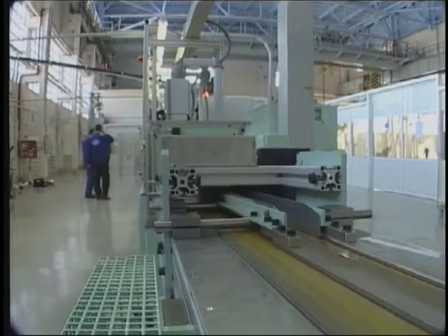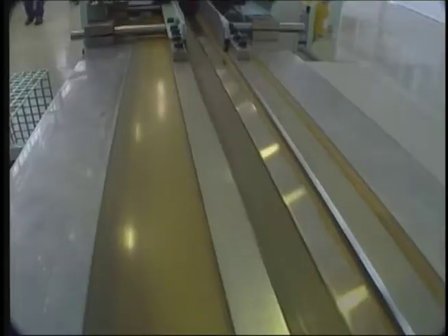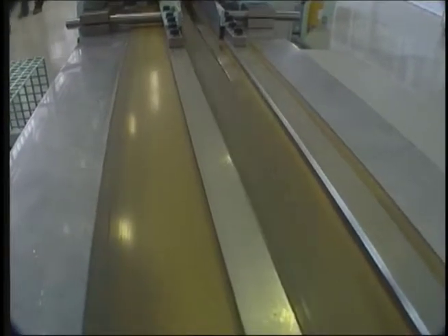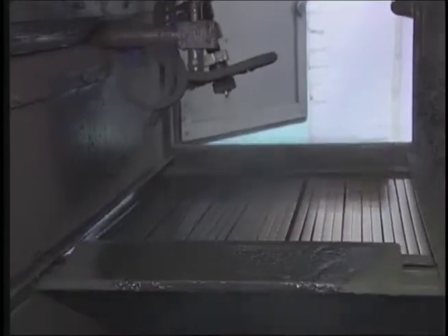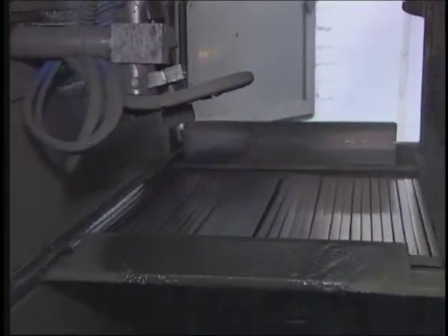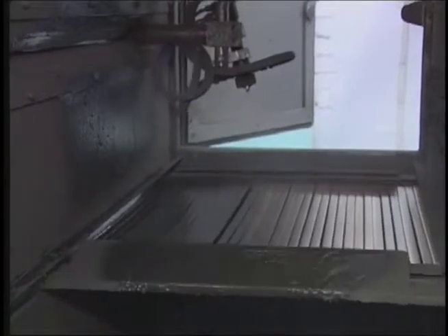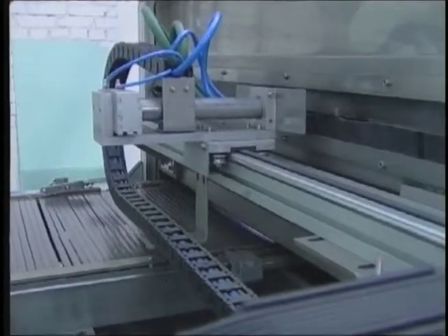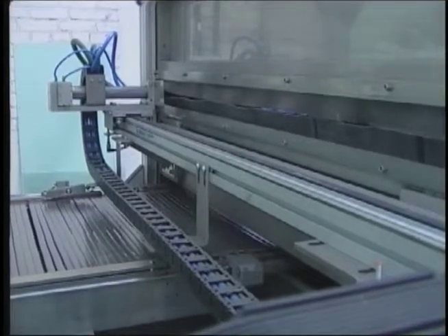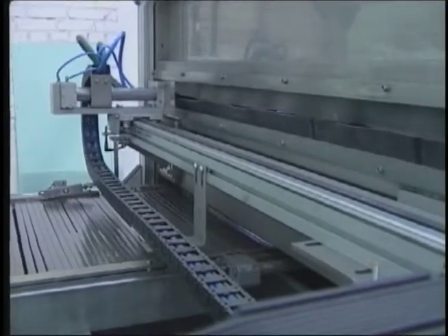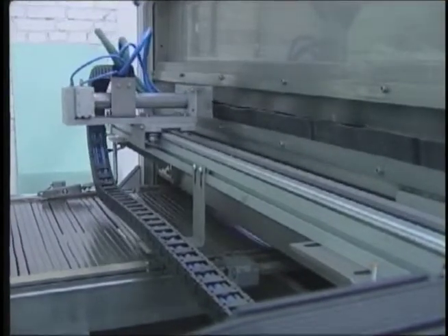The cut sections of tubing are lined up in preparation for spray coating with the brazing material. The brazing alloy is sprayed onto the external surface of the tubes using a tube spray application machine that ensures process uniformity. Once the tubes are sprayed and the coating dries, they can be transported to the assembly area, where tubes and fins are put together into cores prior to brazing.